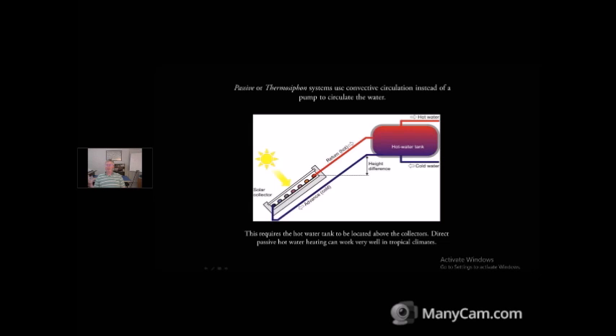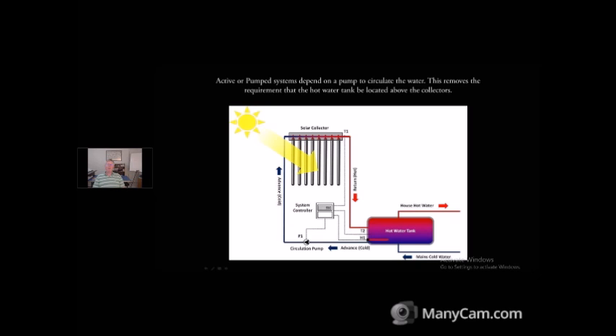You'll probably produce more hot water than you really need year-round. They're fairly inexpensive because it's just not that hard to build. You can kind of do it yourself if you're handy that way. Now an active or pump system is going to depend upon a pump to circulate the water, and that does remove the requirement that the hot water tank be located above the collectors.